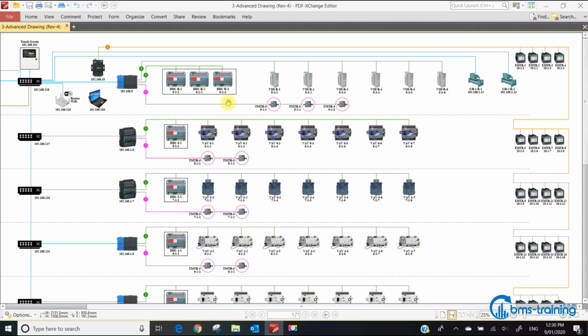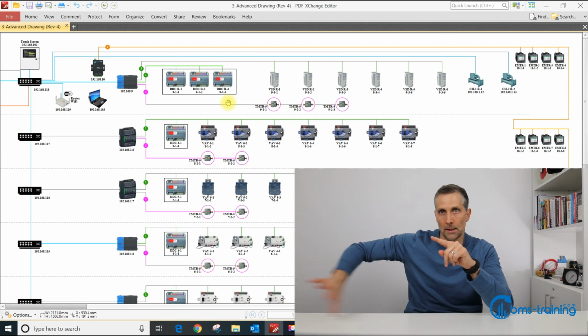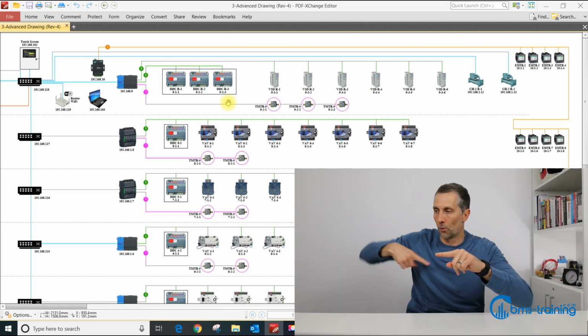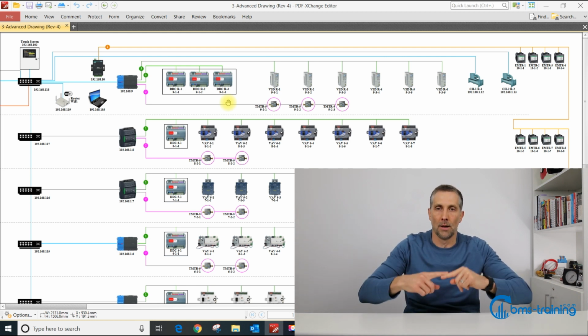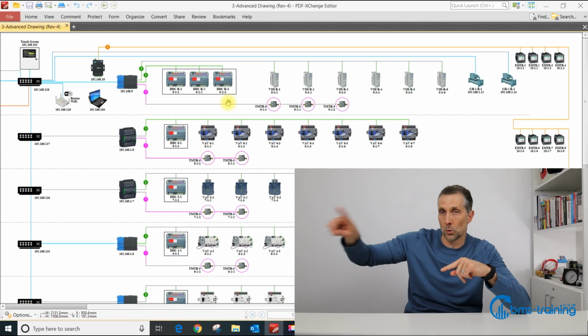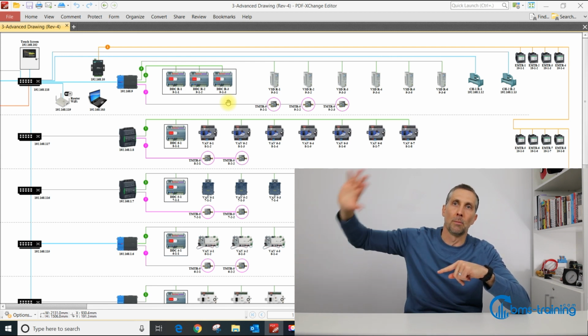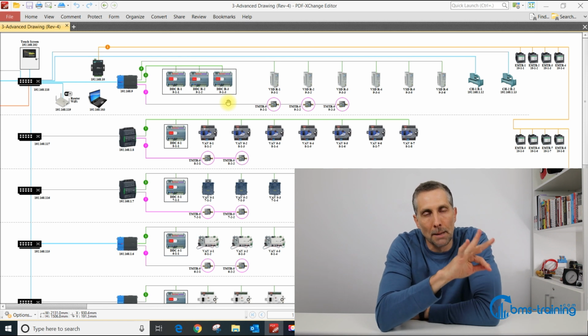You just connect them all together, just as it's designed to do. But when you have a large project, with 500 BMS controllers and 300 electric meters and 200 variable speed drives, you really need to start thinking about how you design your subnetworks. As per this example, we want to have our network controller, and one subnetwork going to BMS controllers in the panel in the plant room, one subnetwork running around the plant room picking up all the variable speed drives, and a third subnetwork picking up the electric meters in the mechanical switchboards, and going up the riser and picking up the lighting power meters up the floor. So we want to have 3 separate subnetworks.